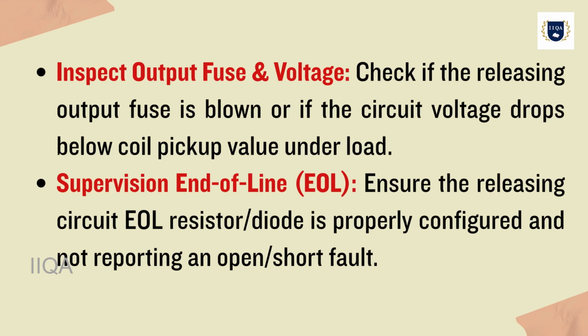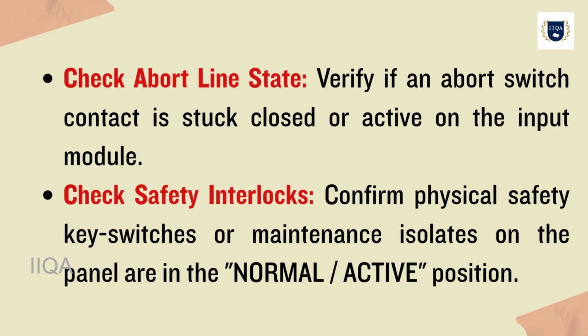Inspect output fuse and voltage. Check if the releasing output fuse is blown or if the circuit voltage drops below coil pickup value under load. Supervision end of line, EOL: ensure the releasing circuit EOL resistor or diode is properly configured and not reporting an open or short fault. Check abort line state. Verify if an abort switch contact is stuck closed or active on the input module. Check safety interlocks. Confirm physical safety key switches or maintenance isolates on the panel are in the normal active position.